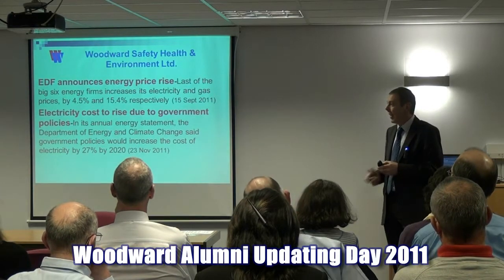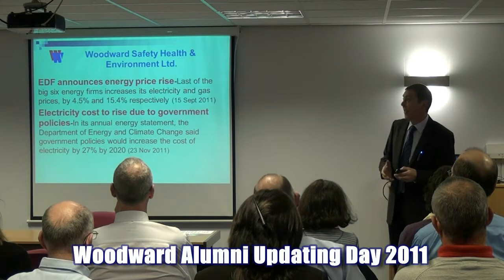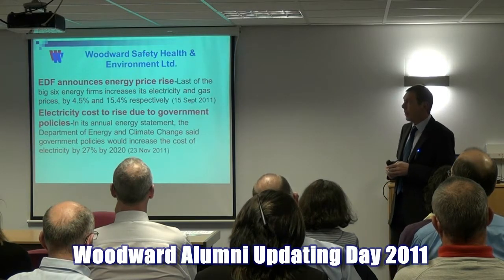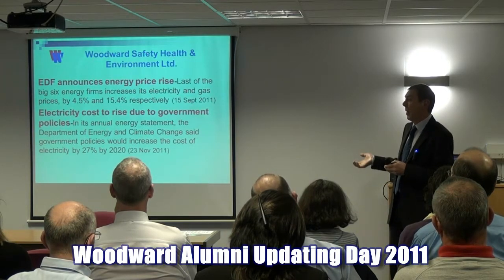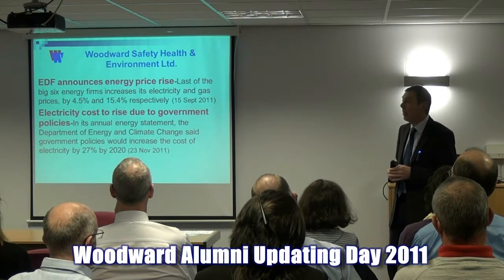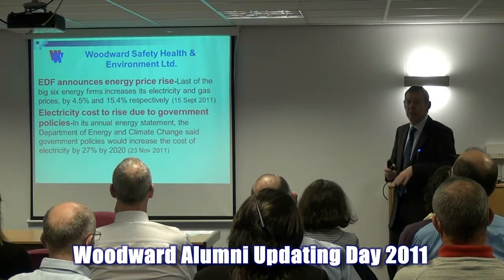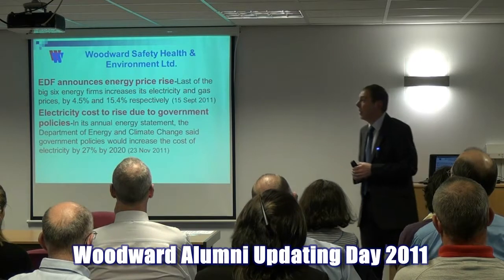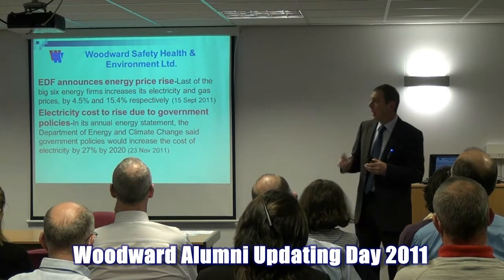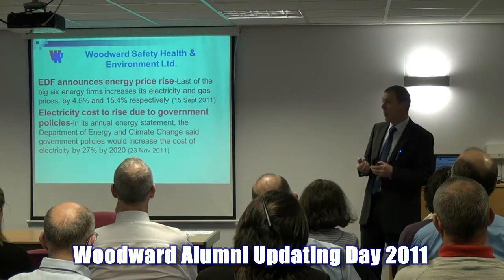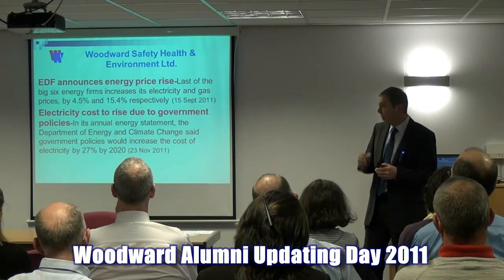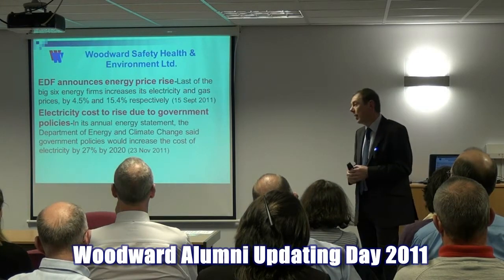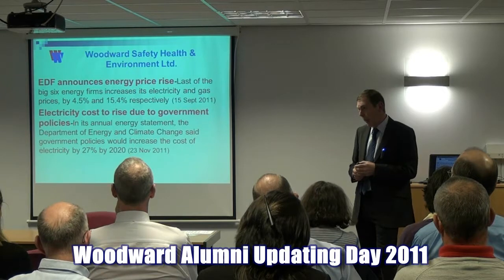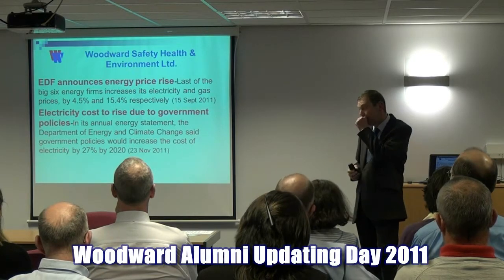You can connect the electricity and hope it survives. You can connect the electricity, and if it doesn't survive, the breaker will come out. What you then have to do is send a team with a cylinder of pressurized inert gas, generally nitrogen. They seal the end of the cable, disconnect it, connect a hose to it, and force the moisture out. I've seen it done with a nitrogen supply to hopefully remove the moisture.